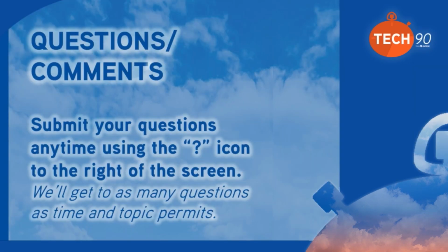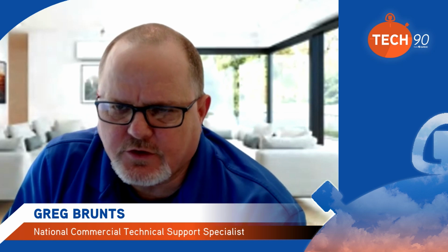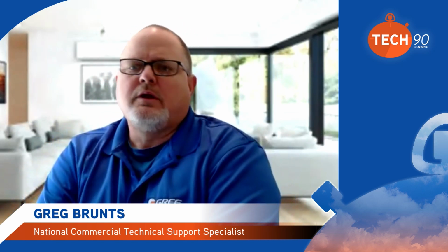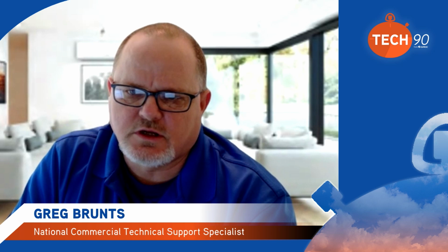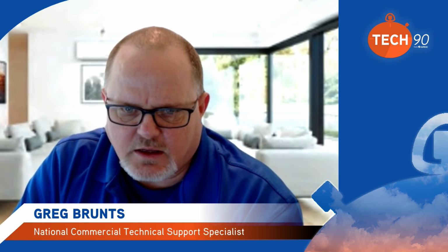Cool. And so I think Cecil was just circling back on the reason why he was asking. He said the reason is, if we wanted one controller for a home that would keep each room at the desired temperature, and I think that's what we already answered, right? It wouldn't necessarily do that. Well, you can do that with a central controller. Right. Okay, so you'd have an individual wired controller or remote for each room. You could have a central controller that would give you one location to go in and adjust the temperature in each zone the way you want it, and only have to go to one controller to do it. So either central control, or in our quick start guide we can show and highlight that a little bit.